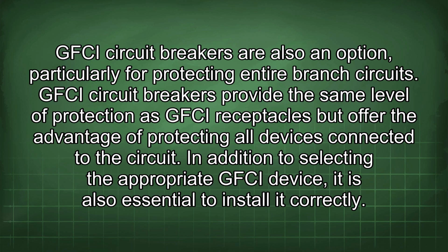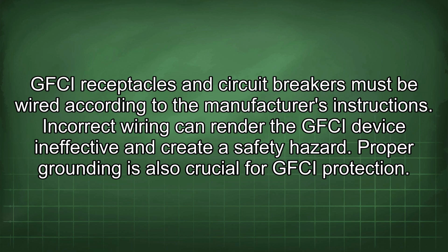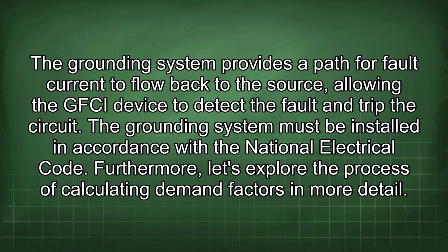In addition to selecting the appropriate GFCI device, it is also essential to install it correctly. GFCI receptacles and circuit breakers must be wired according to the manufacturer's instructions. Incorrect wiring can render the GFCI device ineffective and create a safety hazard. Proper grounding is also crucial for GFCI protection. The grounding system provides a path for fault current to flow back to the source, allowing the GFCI device to detect the fault and trip the circuit. The grounding system must be installed in accordance with the National Electrical Code.